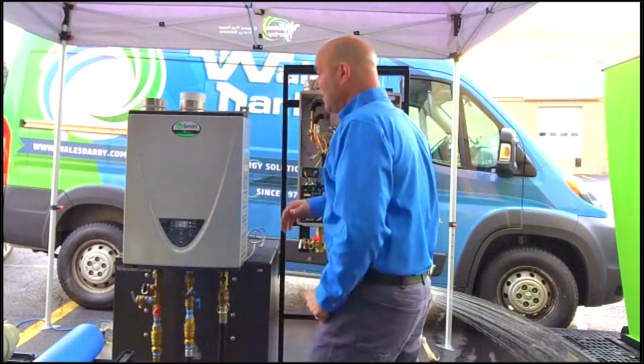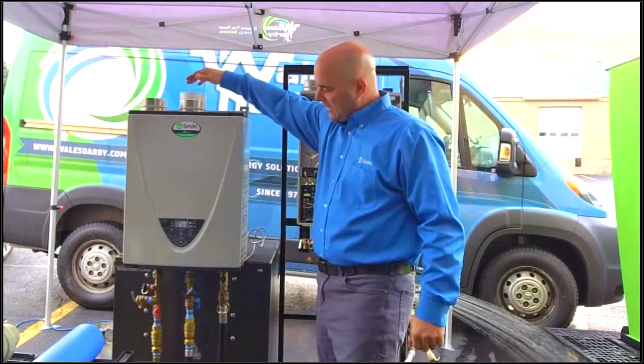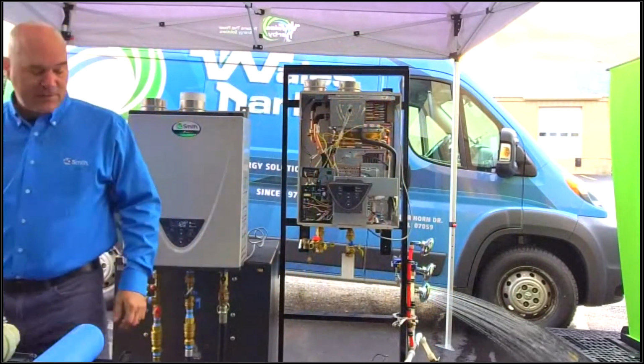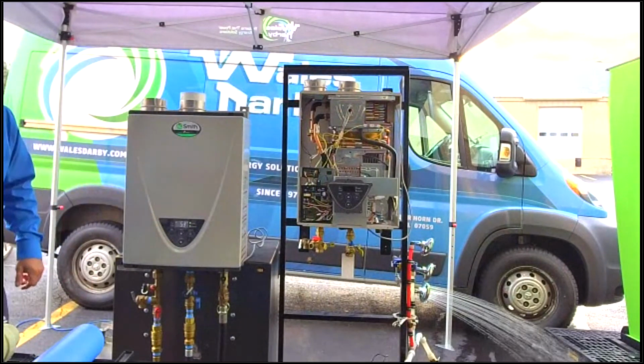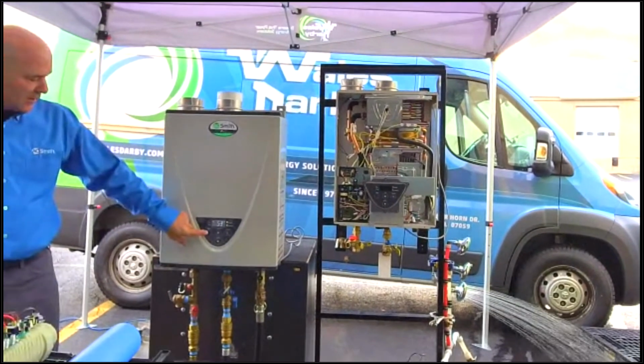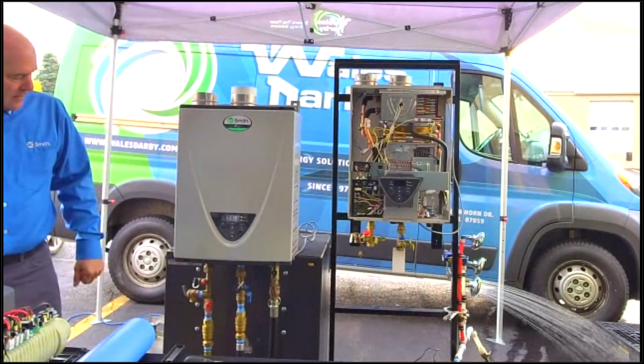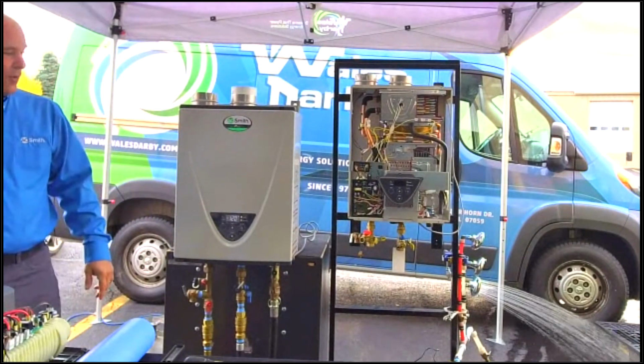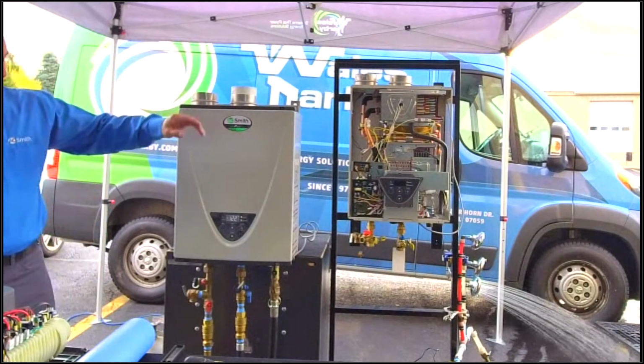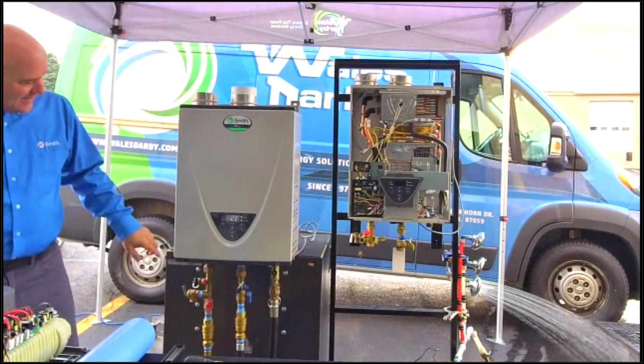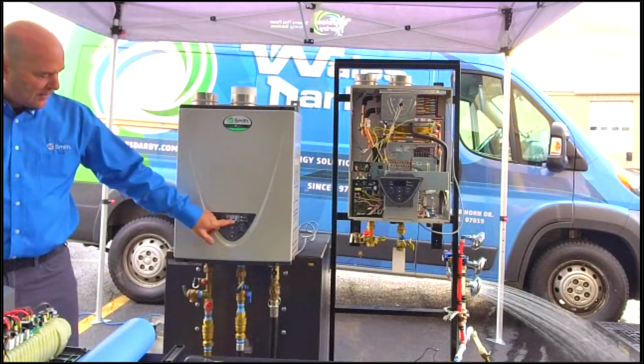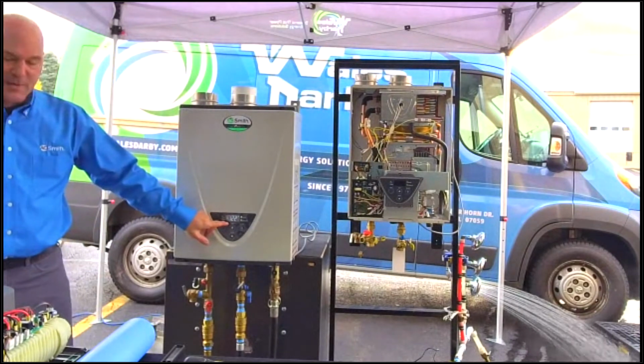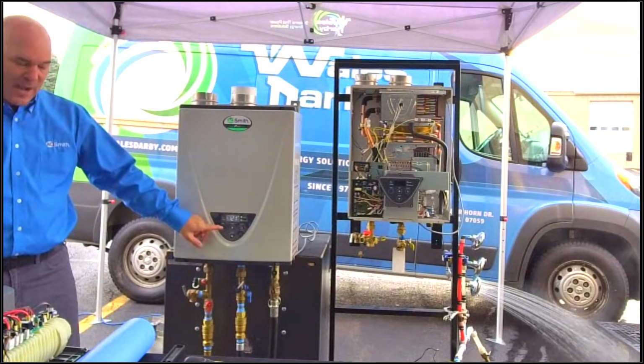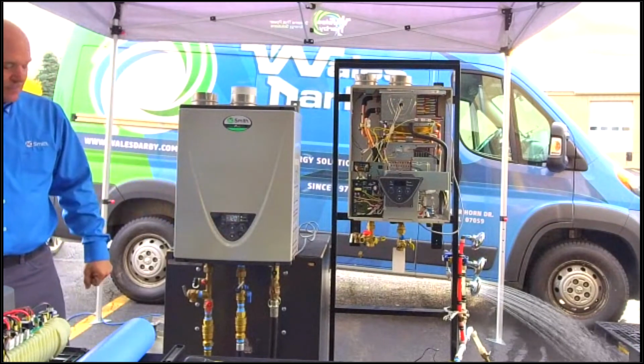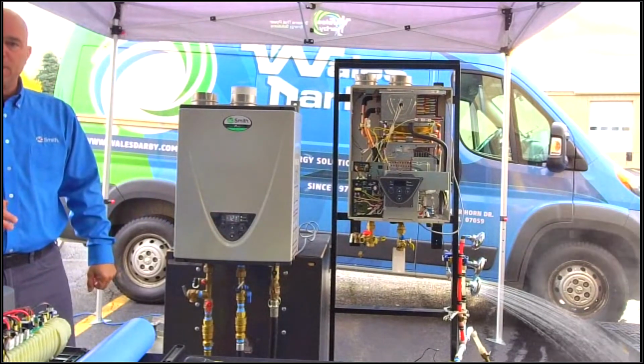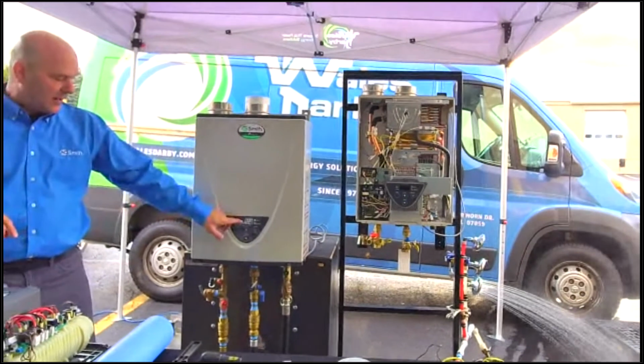Yeah. So the unit has fired, and I got one shower on. I got 53-degree water coming in. I have 120-degree water going out. Say hi to Jim DePalma, taking down our green screen. So we're overshooting target a little bit. We're 123 degrees, 122 degrees. It'll reel it back in. That bypass valve is making the adjustment. Normally on these tankless water heaters, it will always be within 1 degree of your target.